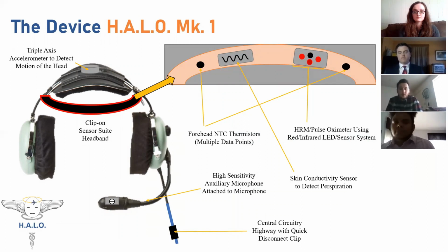contained mostly within a clip on the headband. If we zoom into the headband, you'll notice 2 thermistors used for gathering data on body temperature, and following that is our heart rate and pulse oximeter hybrid sensor, which is designed to monitor the state of the pilot's cardiovascular system optically. A skin conductance sensor is used to quantitatively monitor whether or not an individual was sweating, and a triple-axis accelerometer was used to track head motion for signs of fatigue and other distress. A high-sensitivity microphone is used near the mouth, mounted on the headset microphone, and the sound waveforms were used to monitor respiratory rates.